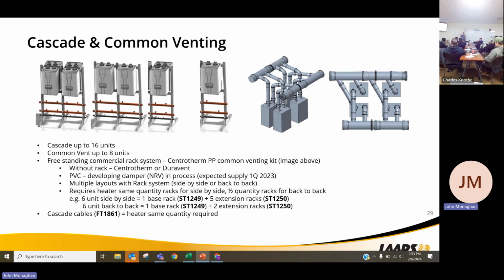Put the units back to back on the racks, two racks side by side. Cascade cables are going to be the same. Need one for each heater. You'll link them all together, set them all up, and it's going to turn on based upon demand.